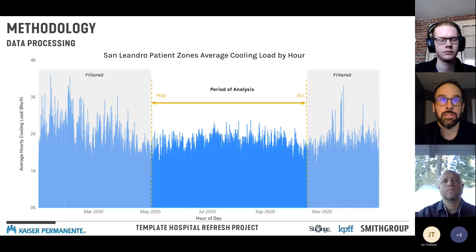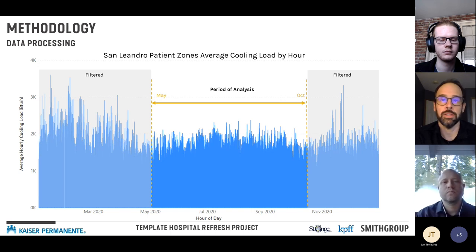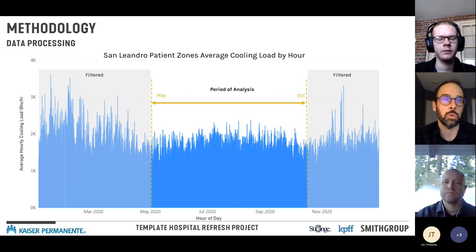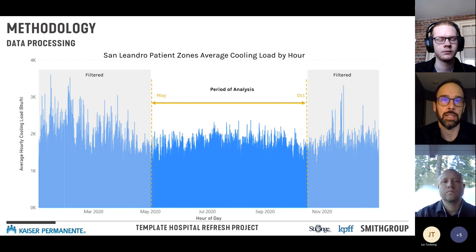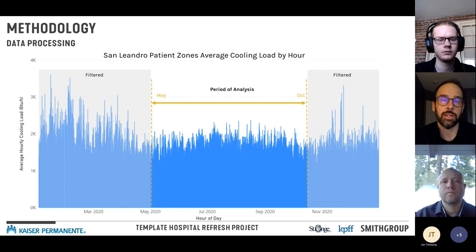A preliminary analysis of San Leandro patient zones showed average cooling load by hour. The gray areas — January through April, and November through December — showed unexpectedly higher-than-normal cooling levels for cold months. We decided to filter those out and focus on May through October. The reason those averages were higher was that a few zones were cooling during surprising periods — likely a controls issue we didn't want to delve into for this analysis.